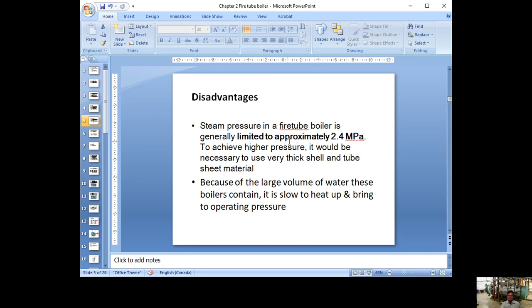One problem is pressure — the fire tube boiler cannot go really high. The maximum is about 2.4 MPa, but in practice most operate around 200–300 PSI, maybe up to 2.0 MPa. If you want higher pressure, the shell metal has to be really thick — five to six centimeters — which is expensive and hard to manufacture. So the construction of a thick shell tube boiler becomes uneconomical at higher pressures.